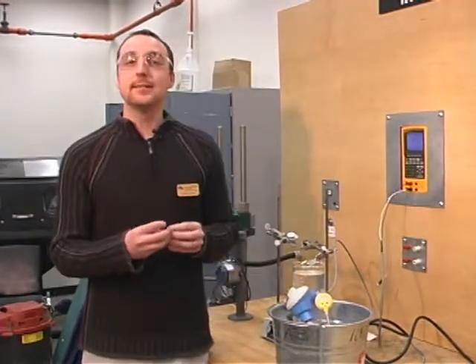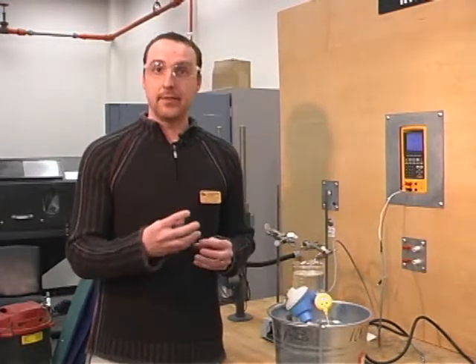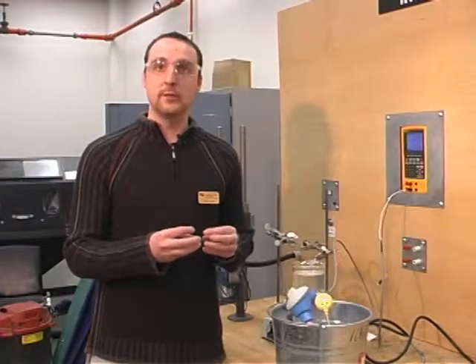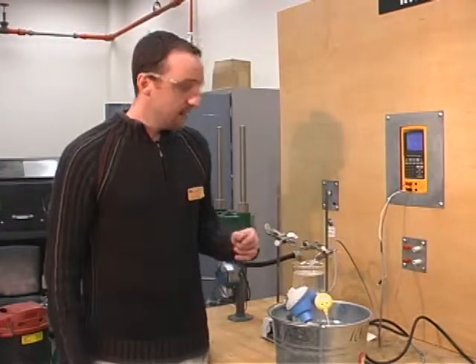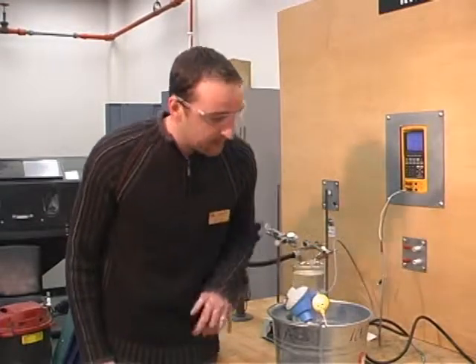The RTD is placed inside a thermal well, so we have to wait till that metal on the outside, the thermal well, becomes around the same temperature as the inside, which is the RTD. Right now, we are reading negative 0.5 degrees Celsius and currently reading 100.9 ohms.